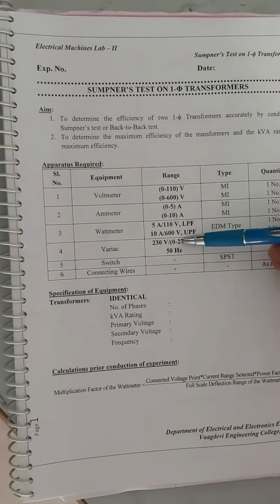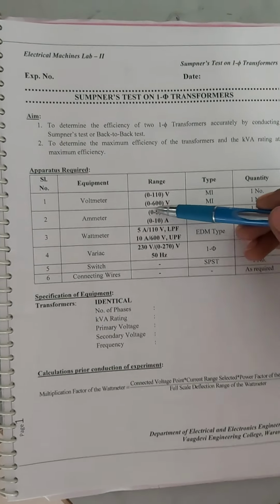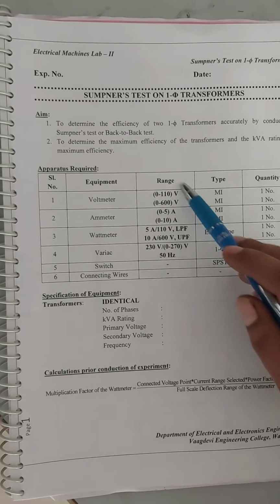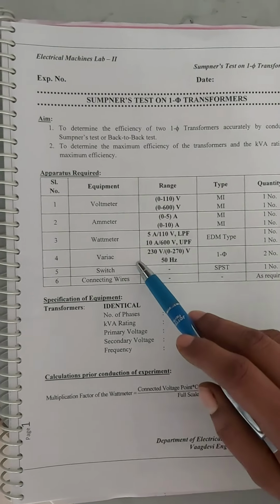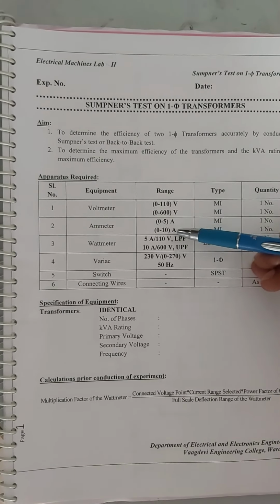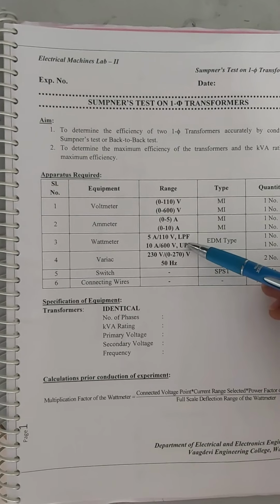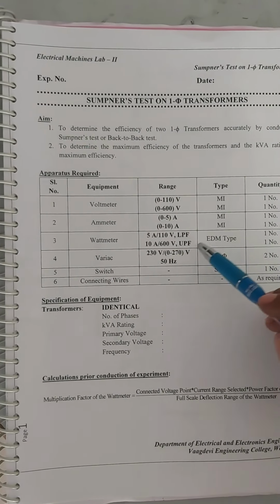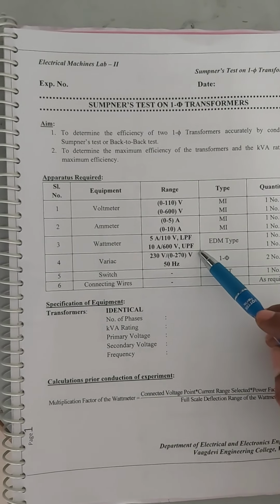Here we are using two meters, 0 to 110 volts and 0 to 5 amperes, and an LPF wattmeter to conduct the OC test on the primary side, and a 600 volts, 10 amperes meter with a UPF wattmeter. These three meters are used on the secondary side to conduct the SC test on single phase transformers.